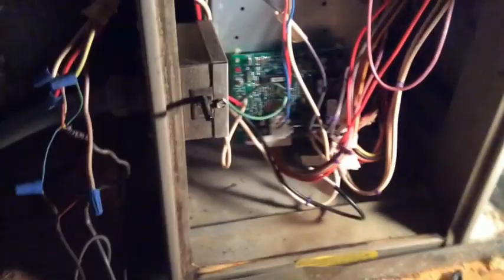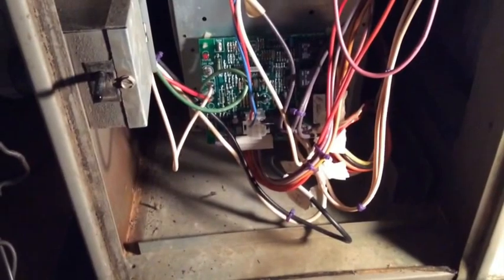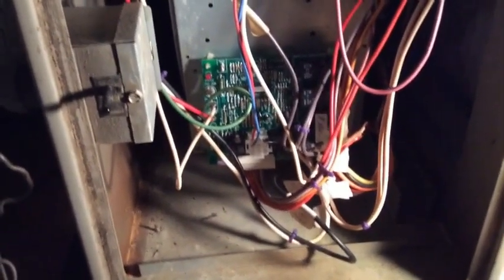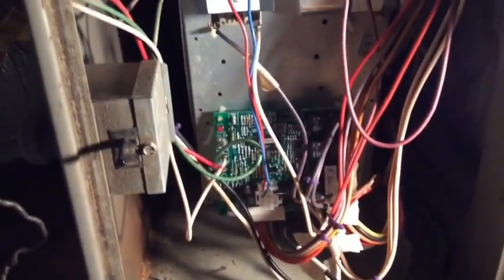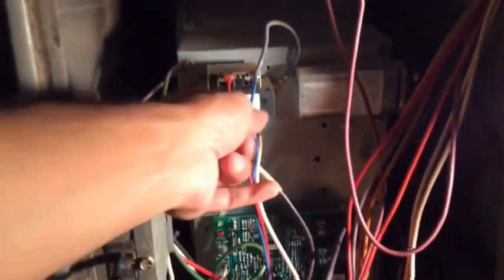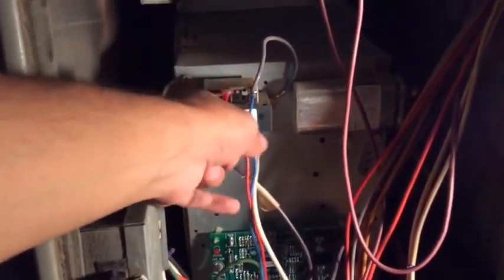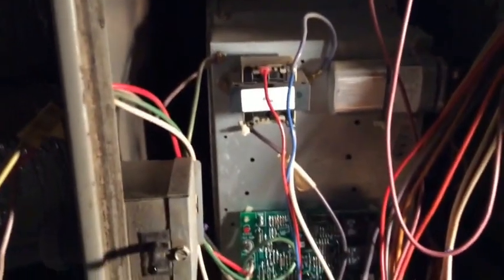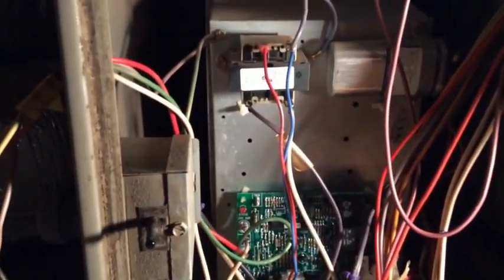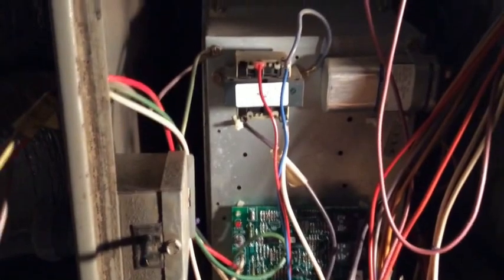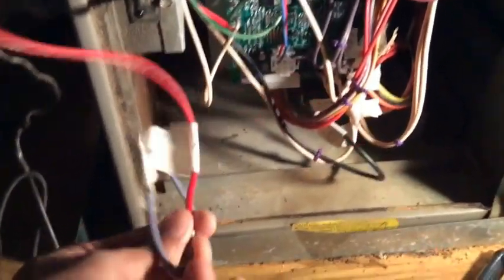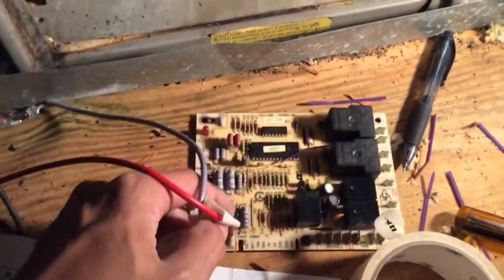Okay, so we've got everything hooked up. The only thing that was a little bit confusing was hooking up the secondary side of the transformer, which is actually what hooks up here. This is the ground, and it's asking you to connect the 24 volt that comes from the secondary. You take that wire, which is this one here, and it hooks up here on this board, 24 volt, right here on this board.